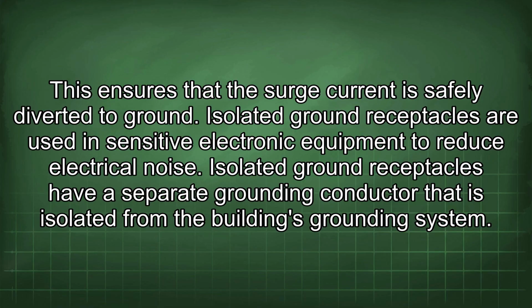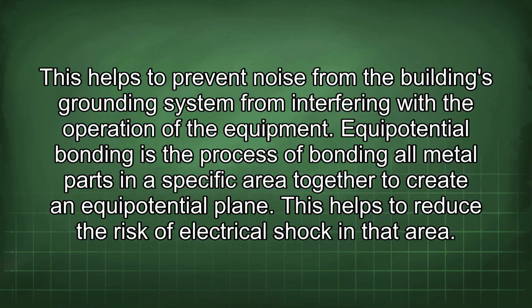Isolated ground receptacles are used in sensitive electronic equipment to reduce electrical noise. Isolated ground receptacles have a separate grounding conductor that is isolated from the building's grounding system. This helps to prevent noise from the building's grounding system from interfering with the operation of the equipment.